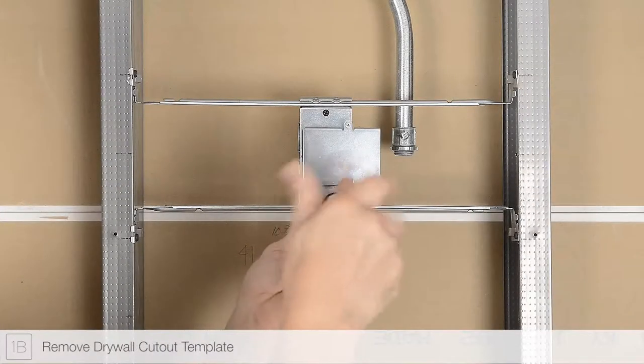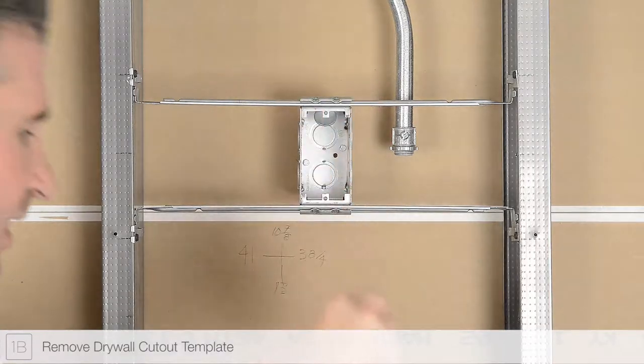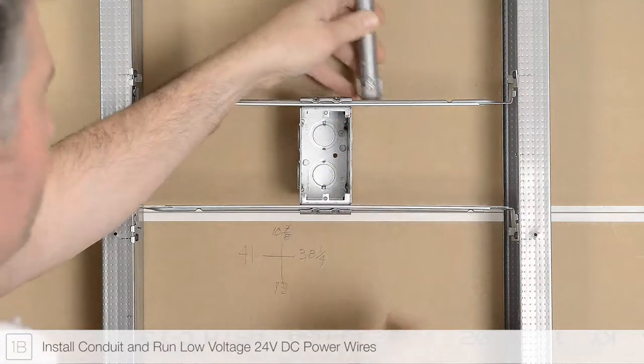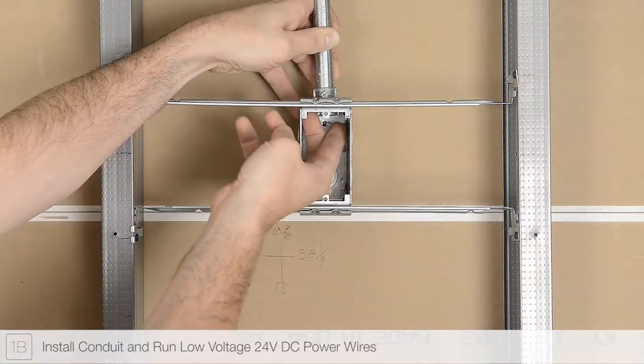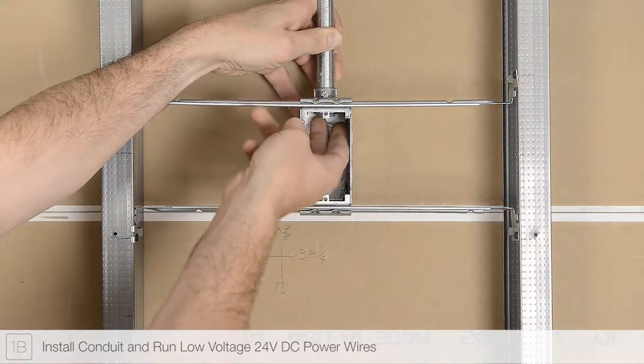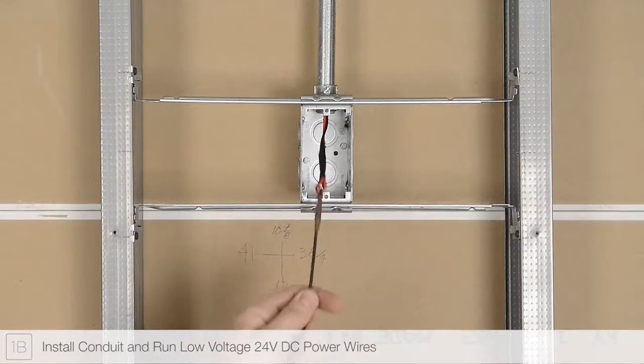Remove the drywall cutout template from the junction box. Remove a knockout from the power feed junction box and, if required by your local electrical code, install conduit. Route the low-voltage power wires from the remote power supply to the power feed junction box.